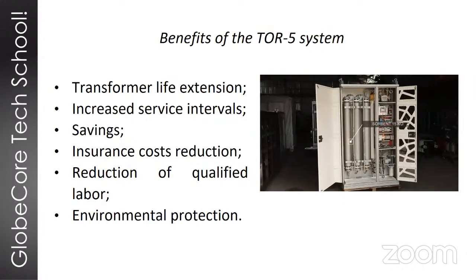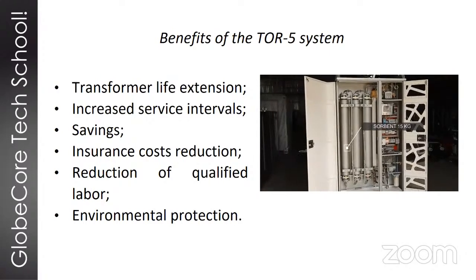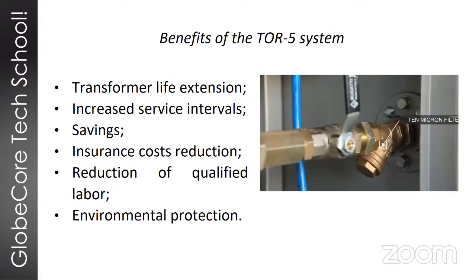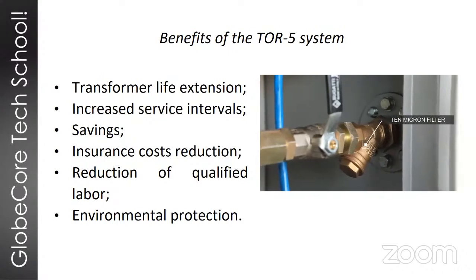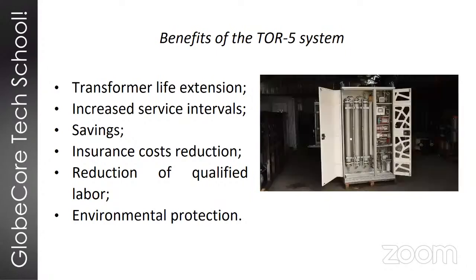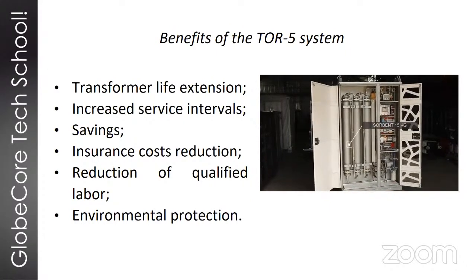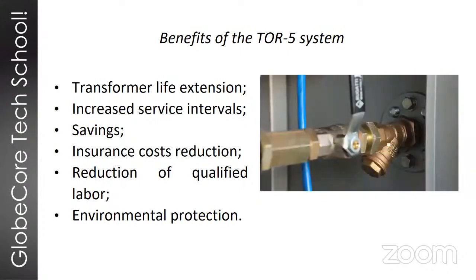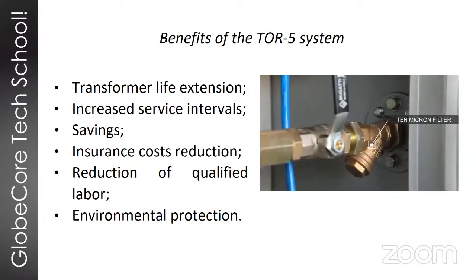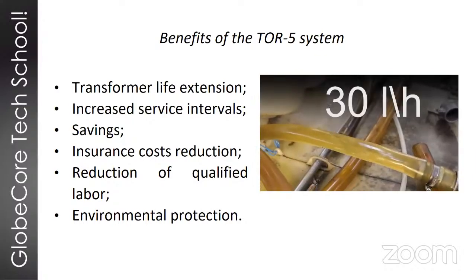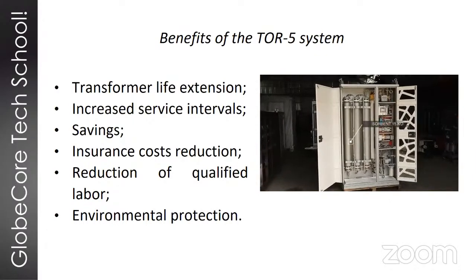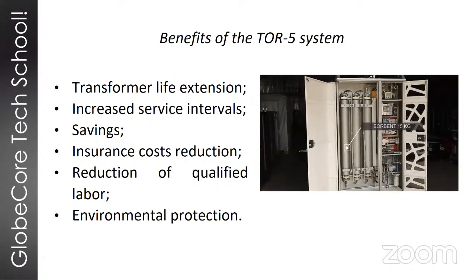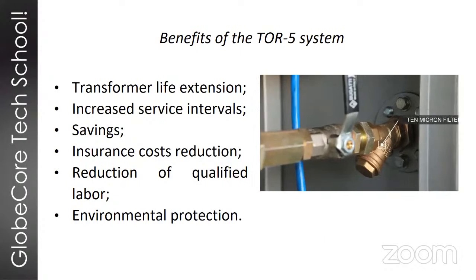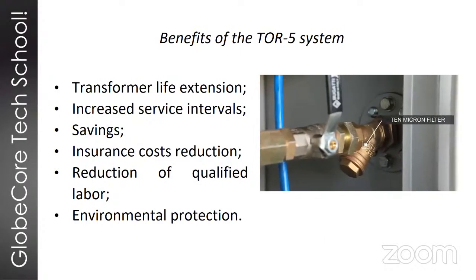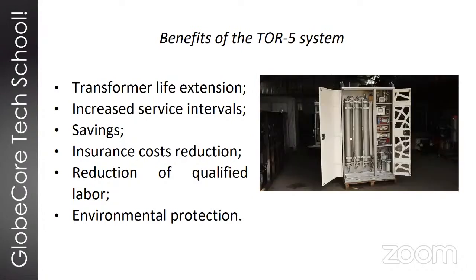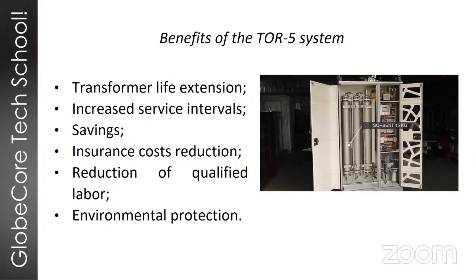Another good thing about it is that it increases, obviously, the service intervals for the transformer by preventively processing transformer oil. It also allows us to save money on laboratory analysis that we would usually do for a good picture of the oil, but this system is advanced enough to give us enough information about the oil to make informed decisions about the transformer. Also, transformer insurance can go down. The probability of transformer failure, if it's equipped with a TOR5, is significantly lower than for transformers that don't have that system. And this usually translates into cheaper insurance policies.